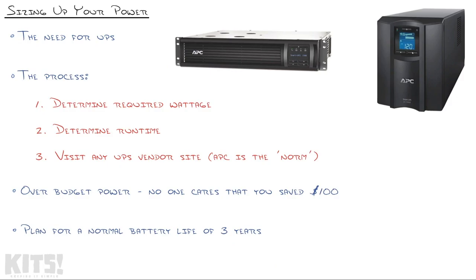Last thoughts on the UPS: first off, over budget power. No one cares that you saved $100. A lot of times we as IT people want to go the budget way and save the company money, going for that short-term win where we come in and say, hey, it's only going to be $400 for the UPS. They're like, wow, the last IT guy said it was going to be $1,200, you're awesome. That's all great until the power goes out and you get like a 3-minute runtime because everything starts shutting down.